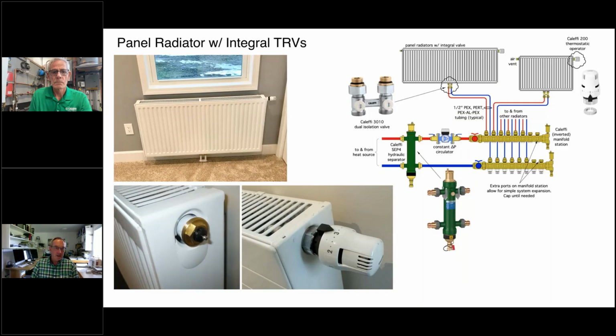And the circulator at full speed that drove the entire house was 44 watts at full speed, and typically would operate 25 to 30 watts. So we had really high distribution efficiency, 10 zone system, room by room temperature control. So each room could respond to internal gains and so forth. And the pump modulates with the valves. As the valves open, the pump speeds up.